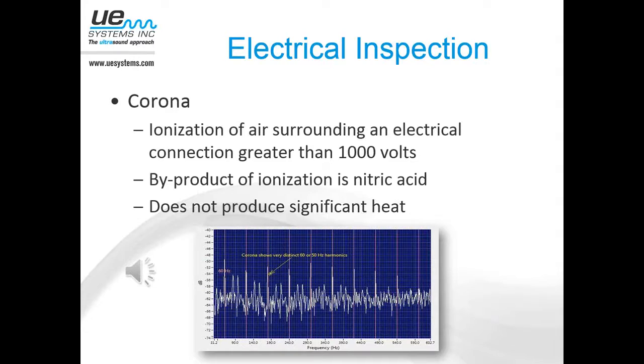The problem with that is, while there is such a thing as what we call nuisance corona, if you go out in your substation on a morning where there's a lot of dew in the air, you're probably going to hear a buzzing noise. That in itself isn't always a run-for-your-life catastrophe. The problem is, if you've got a tremendous amount of corona, one of the byproducts, when you mix moisture and dirt or impurities or dust, which you typically have outside, is nitric acid, which over time is going to break down the insulation material. Then that corona, left unchecked, can turn into something more severe, like tracking or arcing. It also doesn't produce significant heat, so usually you're going to miss that with an infrared scan.